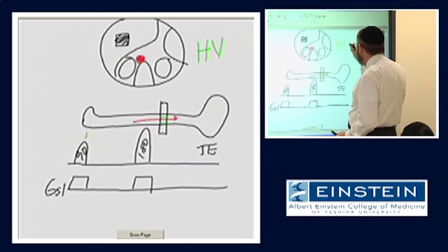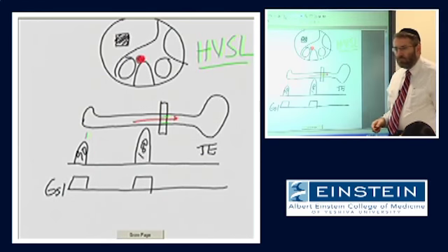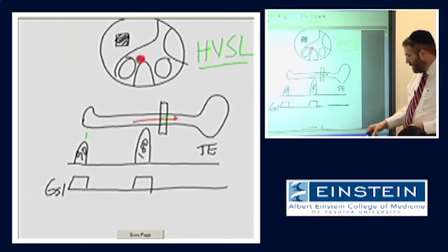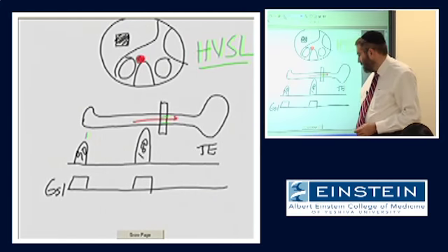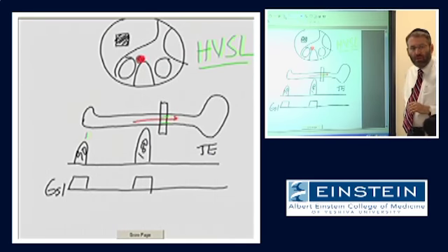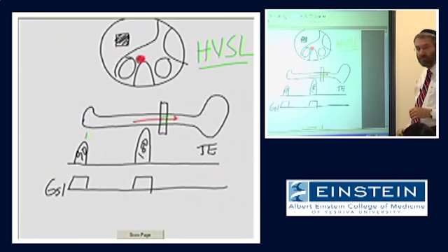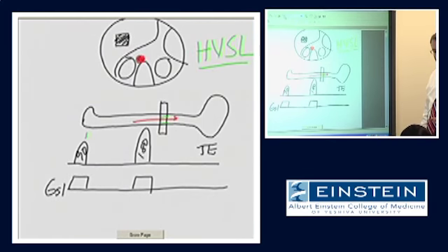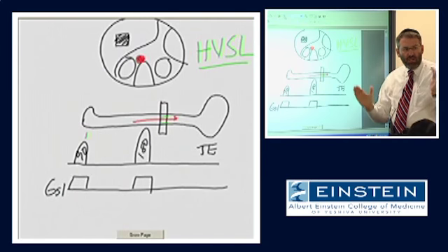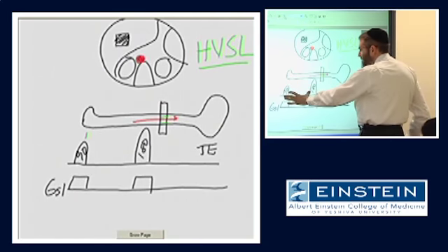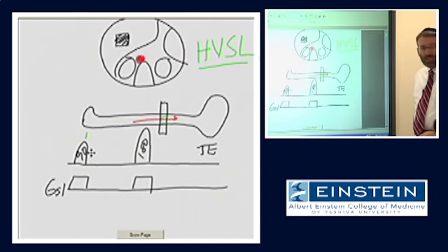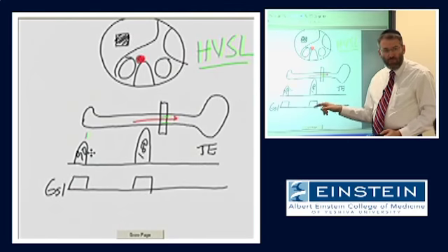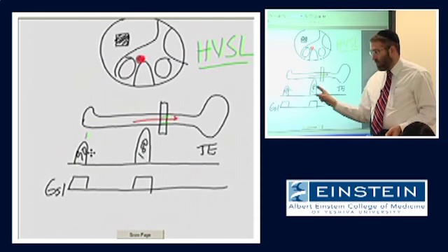Which is why this is called high velocity signal loss. What imaging parameter might affect the likelihood of seeing this? TE — because TE determines the time point that your 180-degree pulse is implemented. As our TE gets longer, the time between the 90 and the 180 gets longer, because the 180 has to be symmetrically placed between the 90 and TE. So as TE gets longer, the likelihood for a given flow velocity that our flowing spins will see both the 90 and the 180 is going to go down.